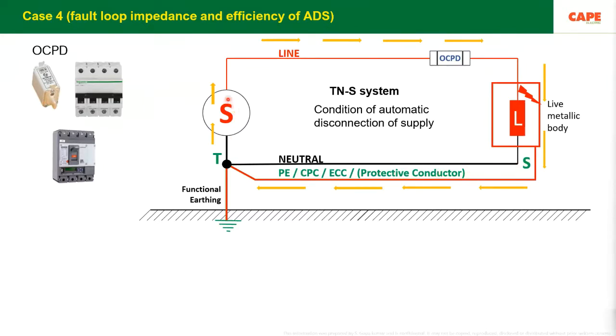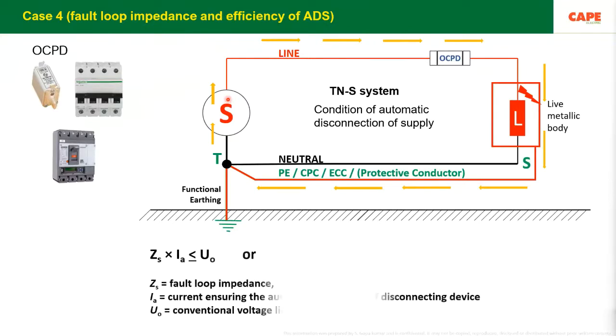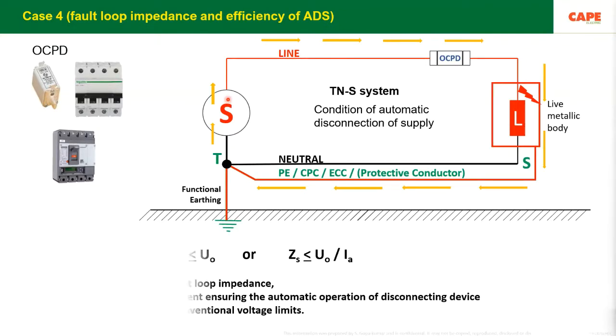Once the fault current is quickly returning back to the source, enough fault current flows and it disconnects the protective device. The protective device will be very efficient. If you have more and more fault current, the protective device will be efficient and the disconnection time will be lesser and lesser. So one of the fourth important points is to ensure that the fault loop impedance is lesser than the allowed limit and the device is able to trip.